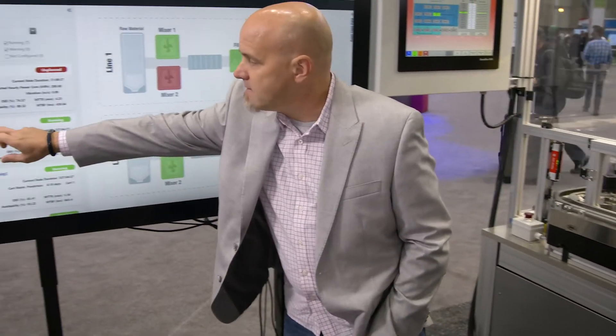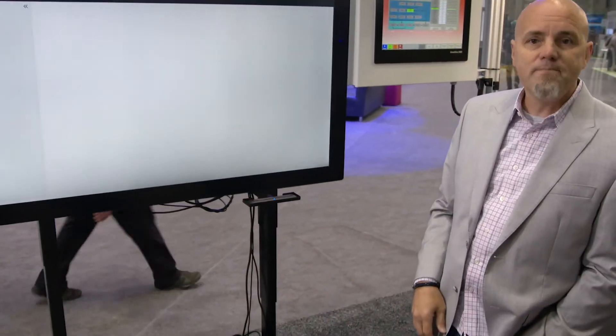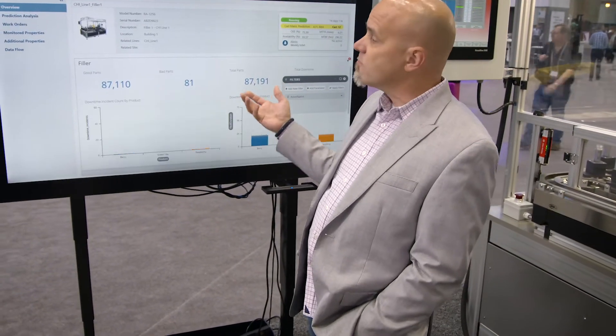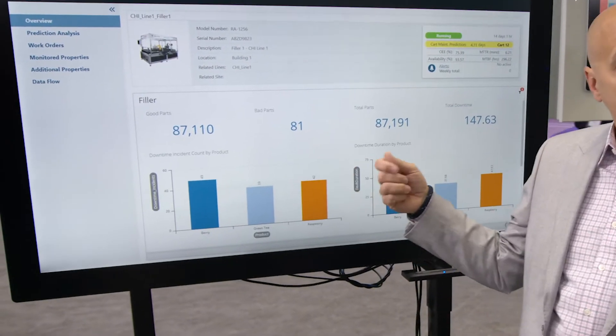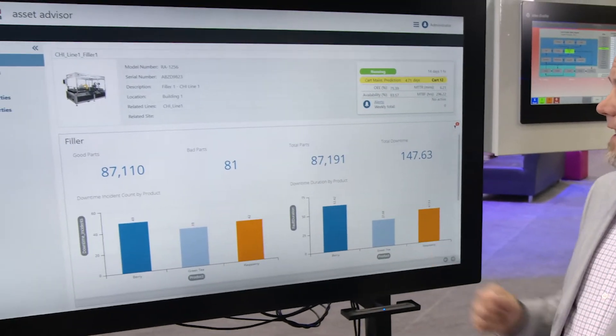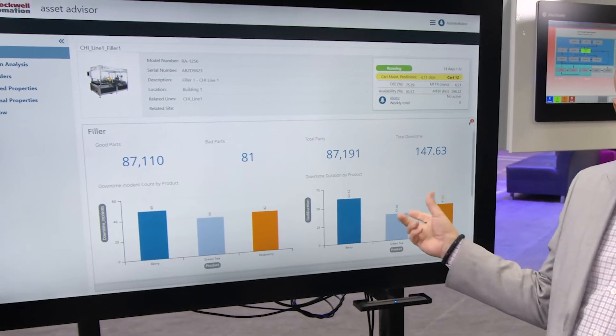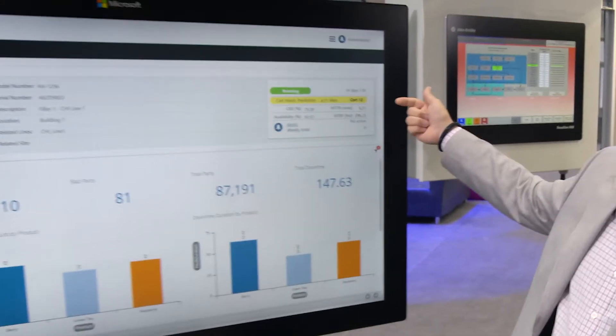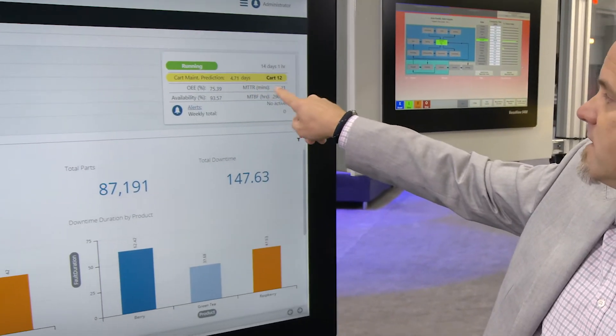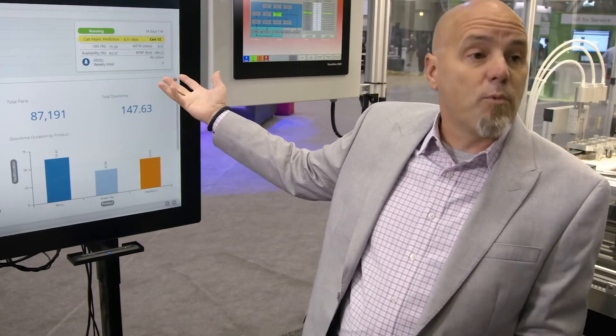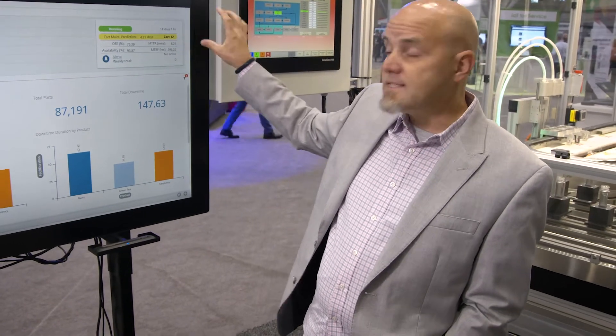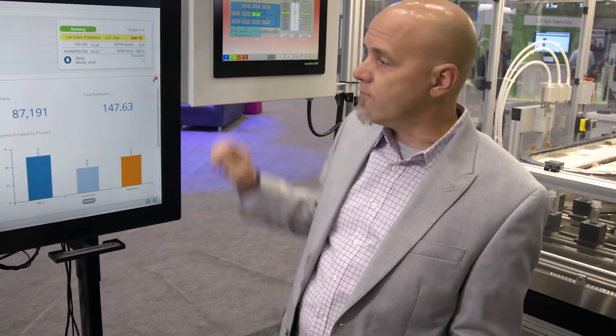Drilling into that and taking a closer look could indicate a problem. Flipping into our asset advisor screen, this is where we start to integrate into Rockwell Automation FactoryTalk analytics and other software components very seamlessly and easily. For example, the analytics is giving us a prediction — a cart maintenance prediction — something's going to fail in 4.71 days. That's direct information into our existing asset advisor application from their software.